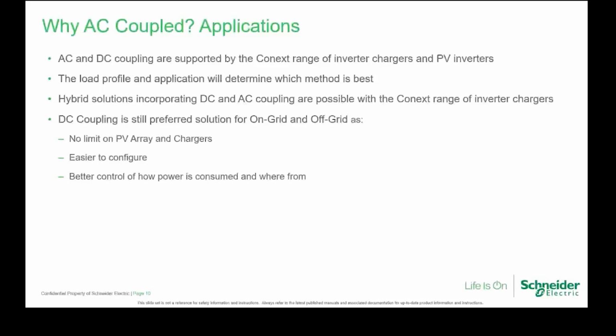DC coupling is the preferred solution for on-grid and off-grid as there is no limit on PV arrays and chargers. It's easier to configure, and you have better control of how power is consumed and where from. We'll go into more detail on the advantages and disadvantages in a second, but it all goes back to where you are with your load profile.